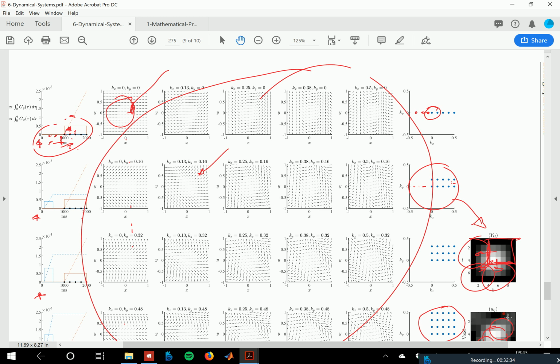But for this example, once and for all: the Z gradient was turned on during excitation. We don't talk about it, we don't see it. The excitation is given 4 times. The Y gradient is turned on to different amplitudes in this time window, and the X gradient is turned on during signal acquisition at this time. Yeah?